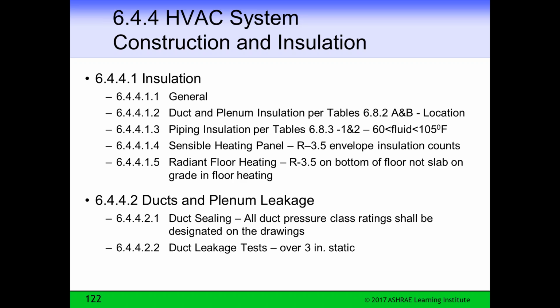We require you to insulate a pipe that has water or liquid cooler than 60 degrees or hotter than 105 degrees, because between those two, 60 and 105, for energy purposes only, you won't pay back the cost of the insulation. Now, there are other reasons you might want to insulate it, such as sweating.